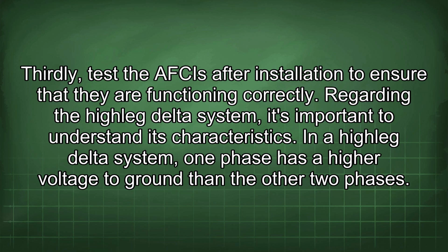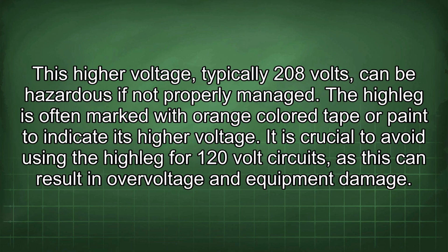Regarding the Highleg delta system, it's important to understand its characteristics. In a Highleg delta system, one phase has a higher voltage to ground than the other two phases. This higher voltage, typically 208 volts, can be hazardous if not properly managed. The Highleg is often marked with orange-colored tape or paint to indicate its higher voltage. It is crucial to avoid using the Highleg for 120-volt circuits, as this can result in overvoltage and equipment damage.